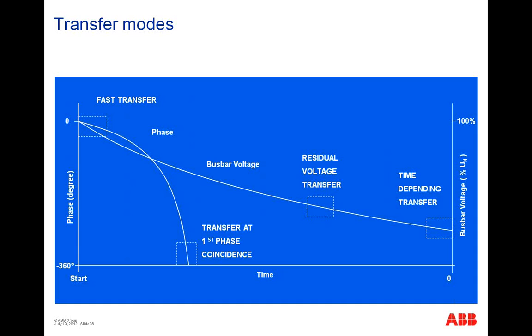They have to call someone. It's not necessary here. At latest, after 2, 3, or 4 seconds, the changeover will be done and all the maintenance guys can start again the production line, and nobody needs a responsible person who is allowed to give commands to the breakers in the medium voltage switchgear.